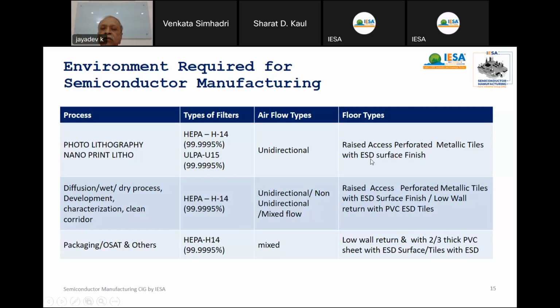So, the type of floor: raised access perforated metallic tiles with ESD on the surface. ESD on the surface is very important, 10 to the power of 5 to 10 to the power of 7 ohm centimeter. And for these raised access floors, we will discuss later what quality and what type of material is used. Next, we go to diffusion processes, dry process development, characterization, and clean corridors. In some cases we can use H14 filters. Some diffusion processes may need reduced flow. For other applications than diffusion and photolithography, use non-unidirectional or mixed flow.